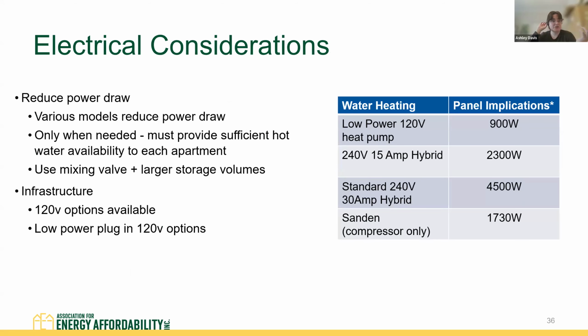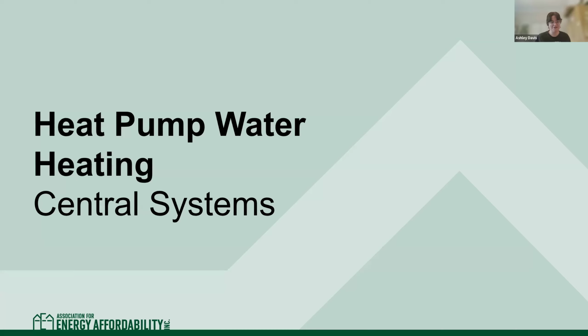And then electrical is something to think about as well, right? Different units have different electrical requirements. Smaller 120 volt heat pumps that don't have backup are going to require a lot less electrical than a bigger, 240 volt standard 30 amp circuit model. So think about what the electrical capacity at the building is, but make sure you choose one that's still going to provide adequate hot water. Next slide. And I'll hand it back to Ari.